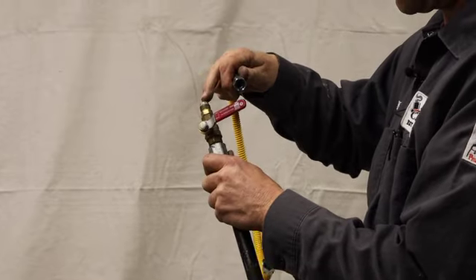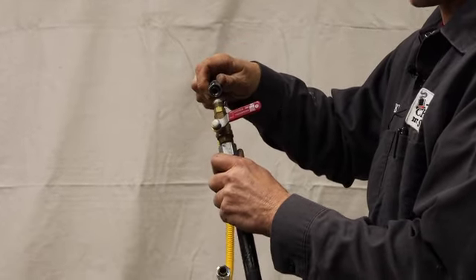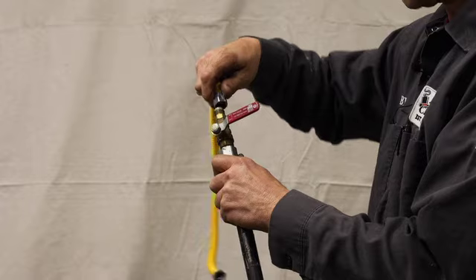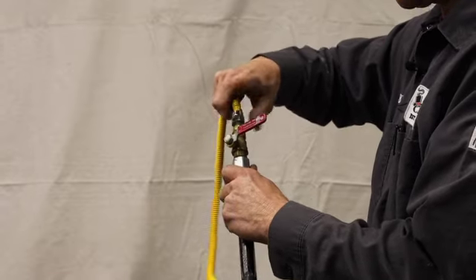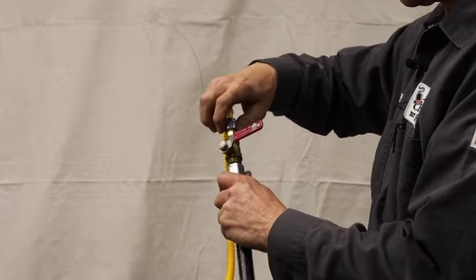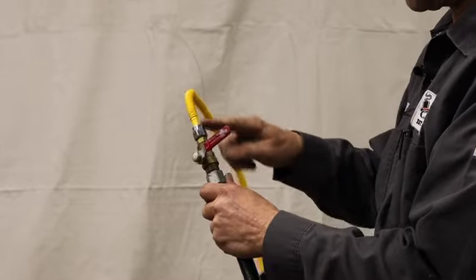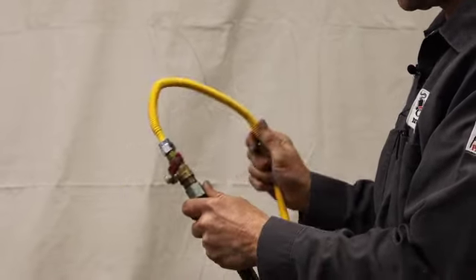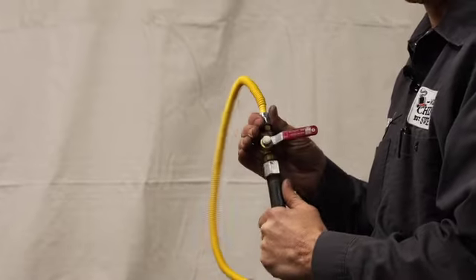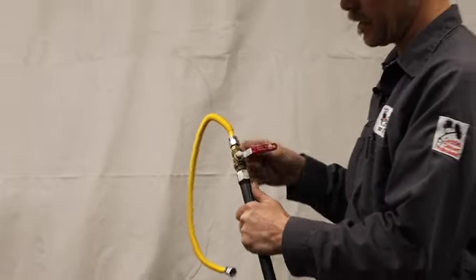We've got a compression fitting on the end, usually always brass, and we have a compression gas flex that will go on there safely. No thread sealant is to be used on compression. So whenever you're using a compression fitting, these beautiful yellow flex lines, do not use any type of thread sealant.